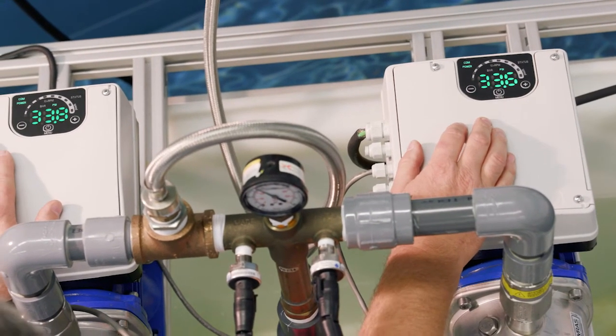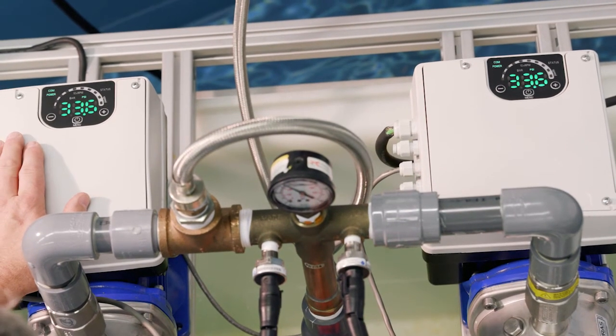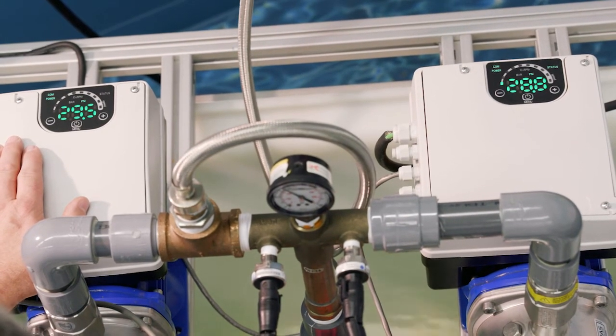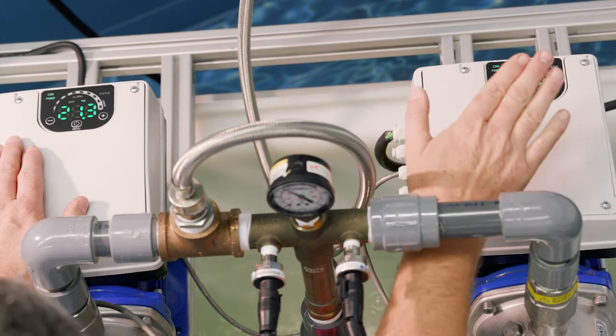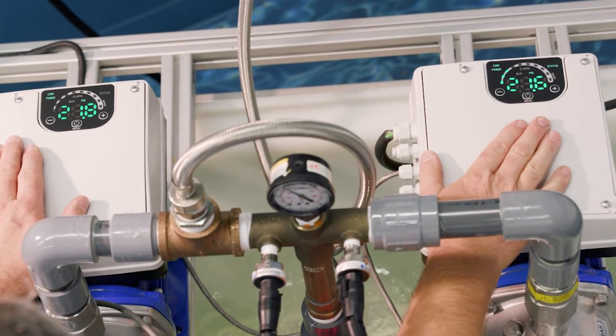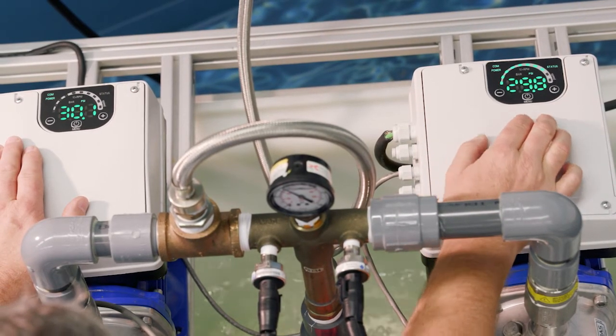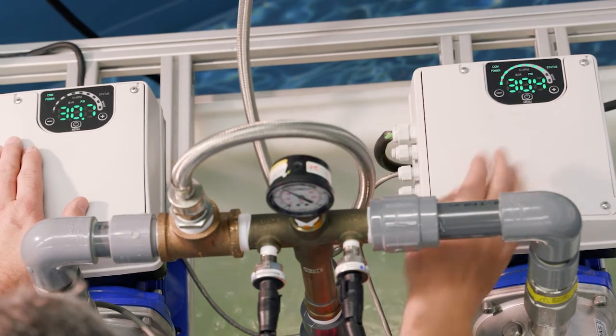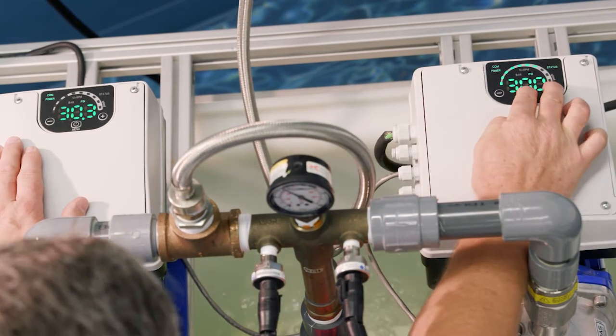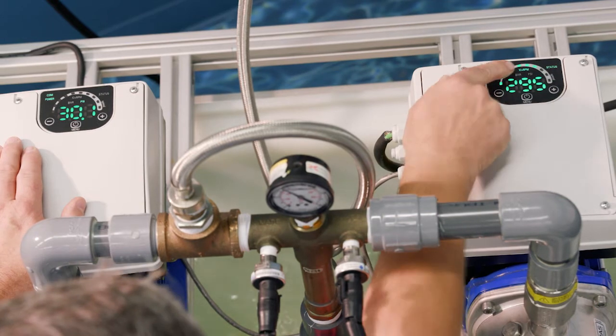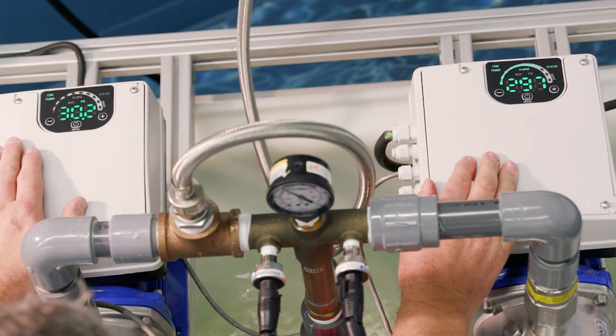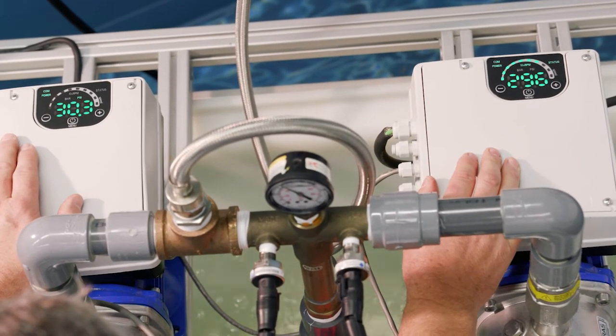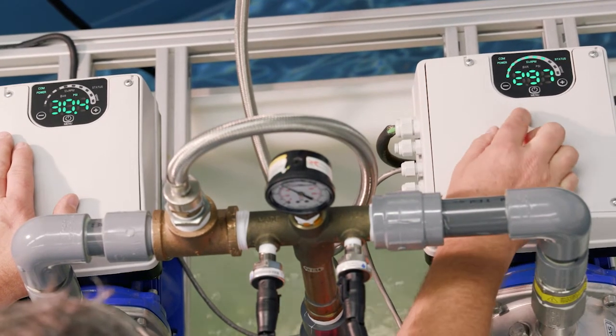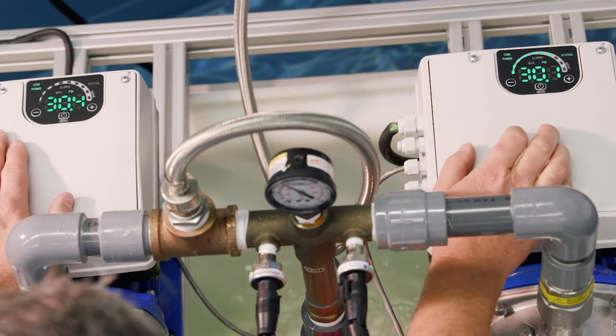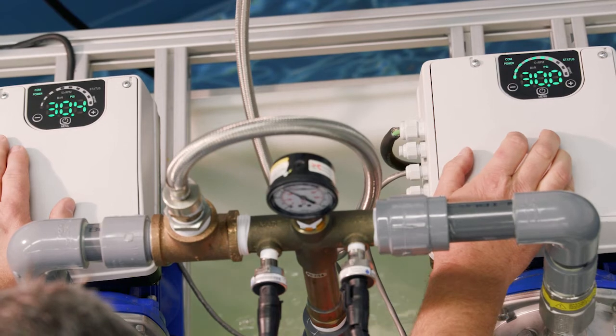All right, so let's go ahead and open up the valve. So we've given it some demand. We can see our lead pump has turned on. And let's take a quick look at speed here. Again, menu plus button. See, it changes to 10 times RPM. Gives us a speed reference. And after a few seconds, it goes back to the default, which is PSI.